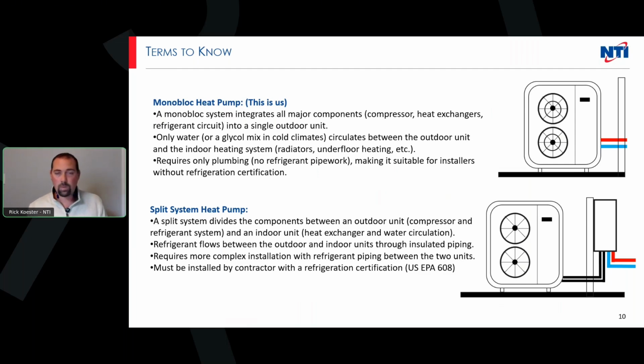Basically, we have two different types of systems out there in the world today. We have monoblock heat pumps, and we have split system heat pumps. Monoblock means that all the refrigerant components are going to be inside that outdoor box, so there's nothing in the occupancy. As you can see in the top there, we're moving warm water in and then returning it back to the machine.